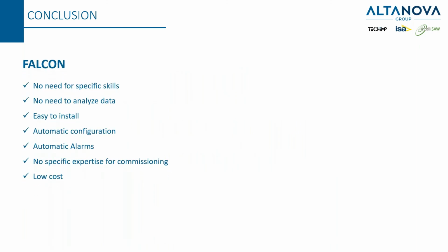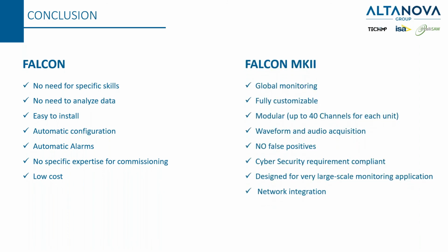If you want to compare the 2 different Falcon, okay, it's mentioned that Falcon Mark I needs no specific skills, no need to analyze data, easy to install, automatic configuration, automatic alarms, no specific expertise for commissioning, and it is a low cost. While the Falcon Mark II provides typically a global monitoring due to the merge of different sensor and measurement value, is fully customizable, is modular, provide the waveform and audio acquisition, is also providing no false positives because the main acquisition policy is the same. It also satisfies the cybersecurity requirement, and it is basically designed for a very large scale monitoring application. And it has also the network integration.